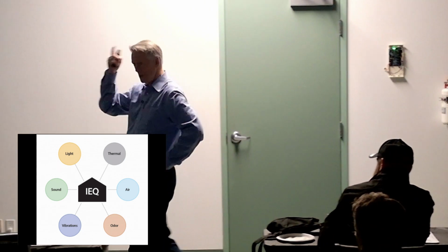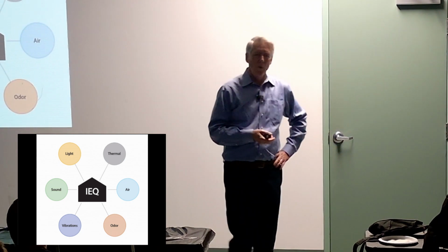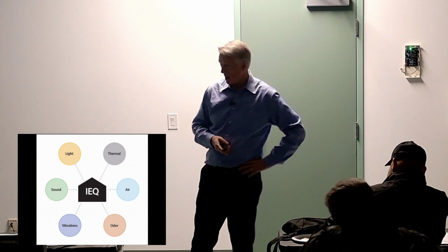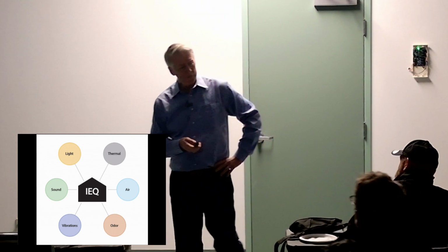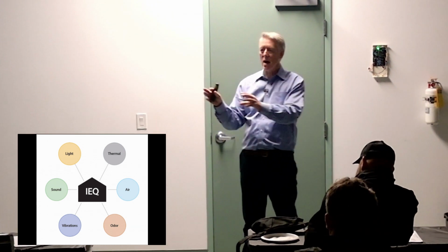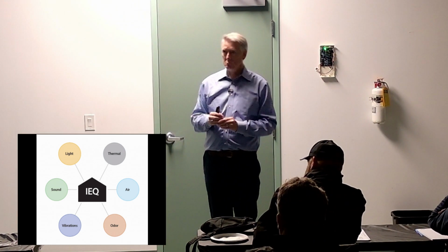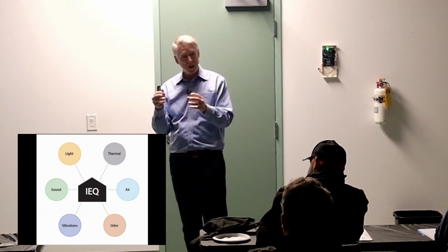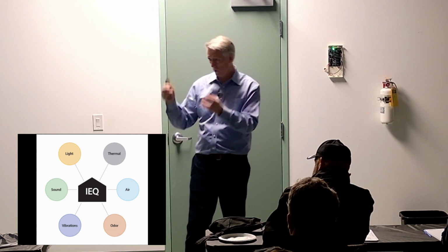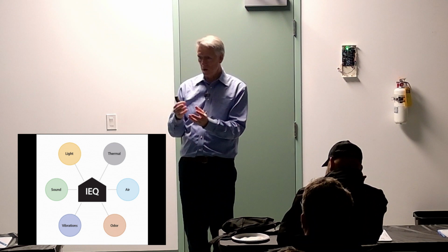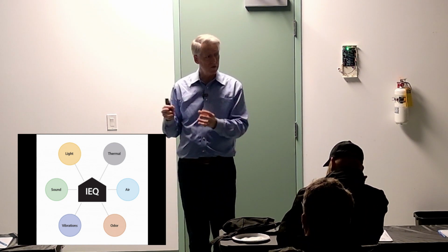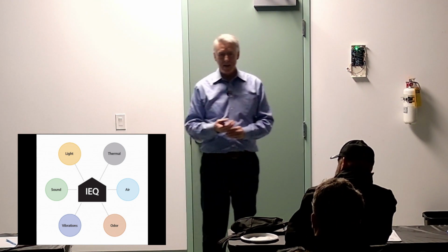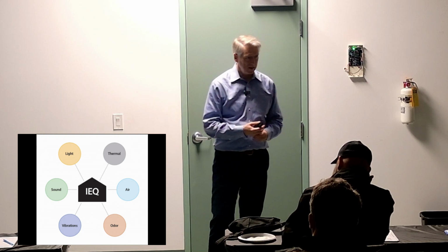Vibrations, the story that goes with that, it's not really a story, but one thing you're seeing more and more now with the heat pump craze that we are in the midst of is outdoor units mounted to the building. That's a good place to put them when it works, but you have to be careful because those things can vibrate. And if you put them on a wood frame structure that has resonant frequencies in line with the frequencies of that outdoor unit, you can get vibrations in the house that are amplified because of that resonance, and that can drive people crazy inside the house.